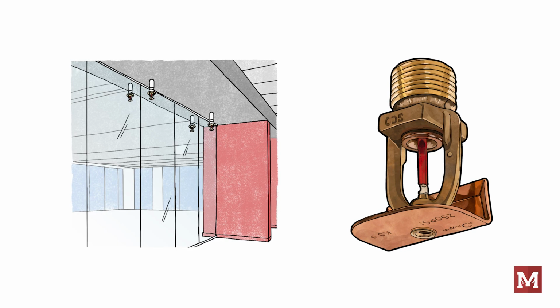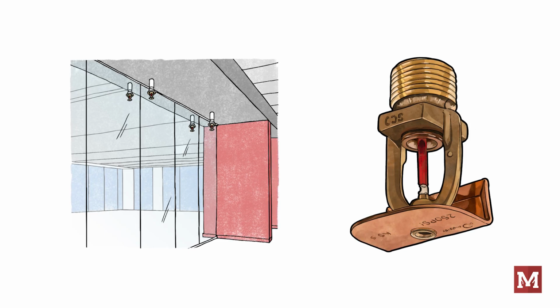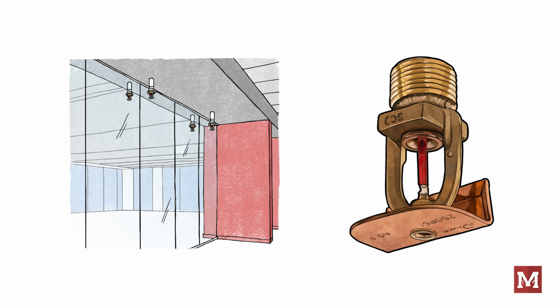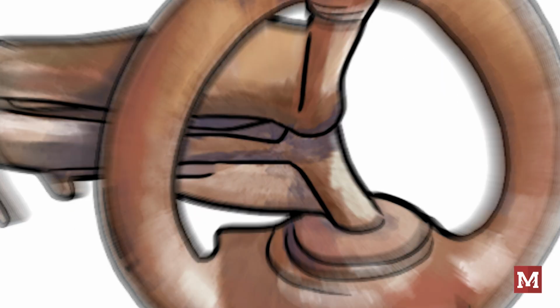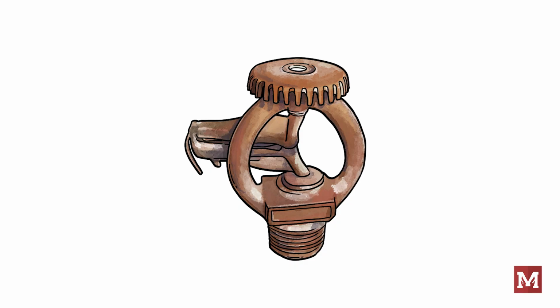These are here to give glass assembly what's equivalent to a 2-hour rating. But you must be careful and follow a very long list of rules that are required to make them work. Using these sprinklers can give architects the look they want, the cost that the owner likes, and we as engineers and technicians can sign off on it. So why use different types of fire sprinklers?